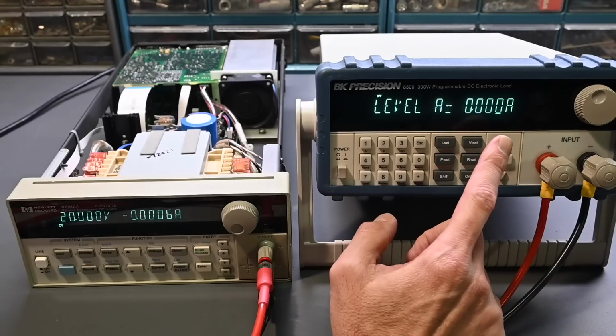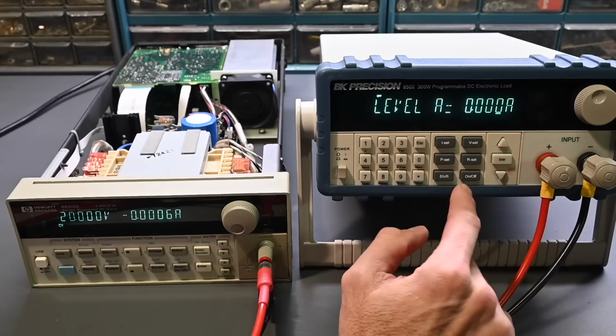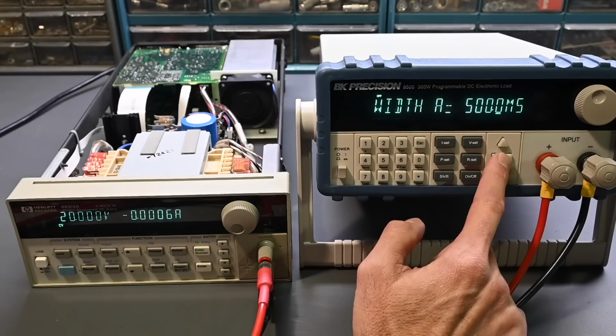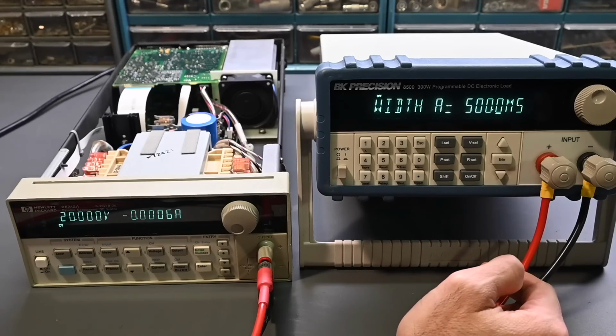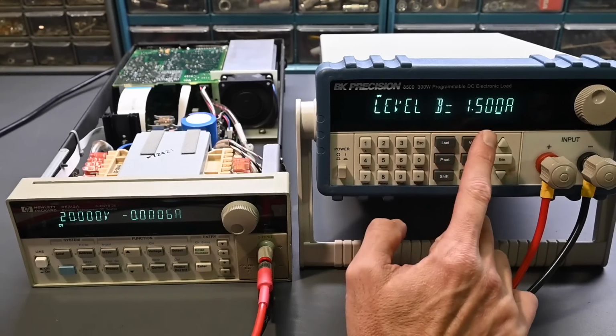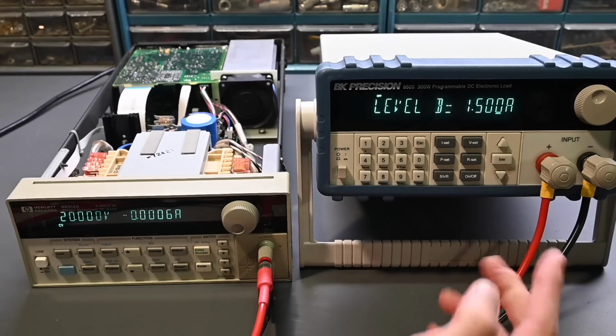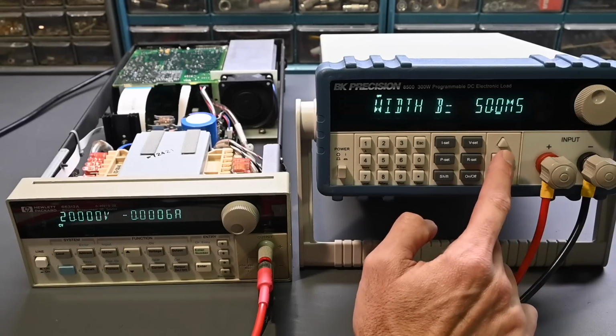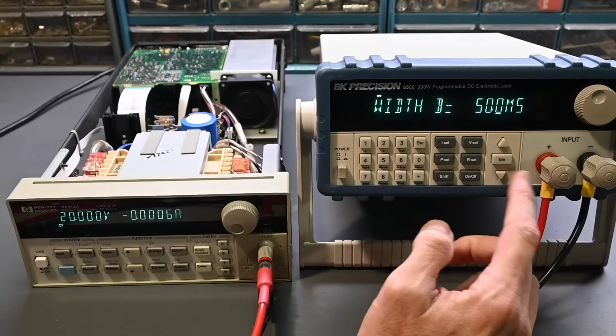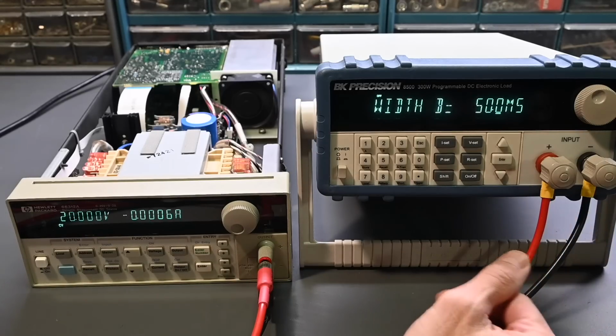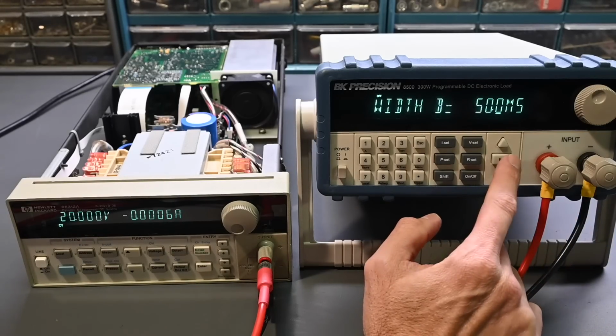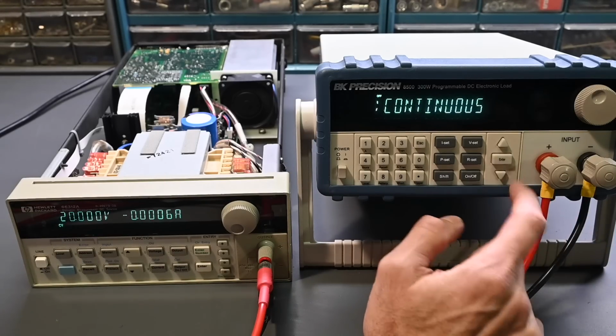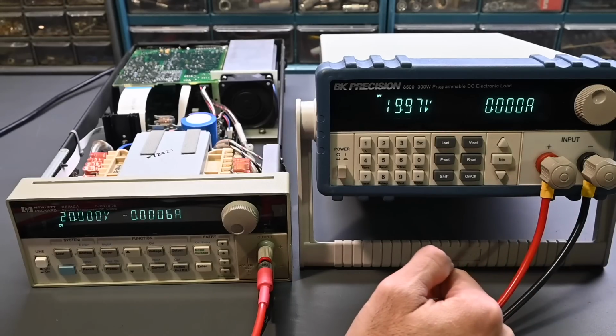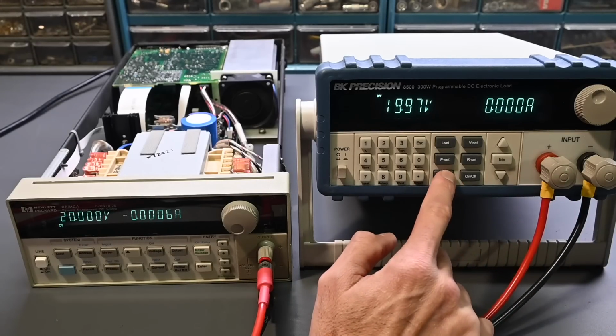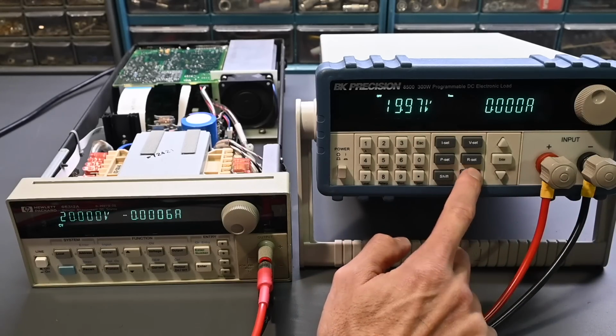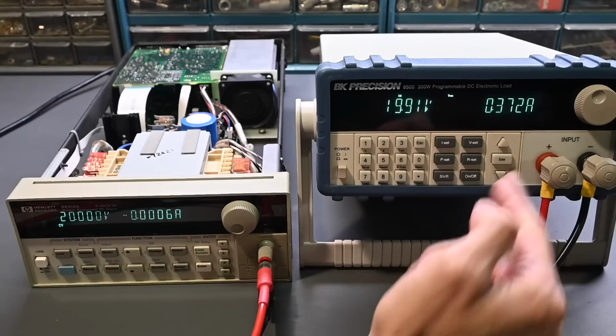So level A, current is no current, so 0, okay? And it remains at 0 for 500 milliseconds. And then the level B is 1.5 amps, so a large step in current, but for just 50 milliseconds, so very, very quick. 50 milliseconds is just a brief pulse. And then it's to be continuous, so it just goes over and over again. All right, so if I go over here, shift, set the transient on, and turn that on. So now that's what it's doing right now, okay?